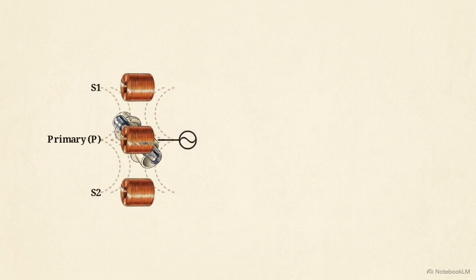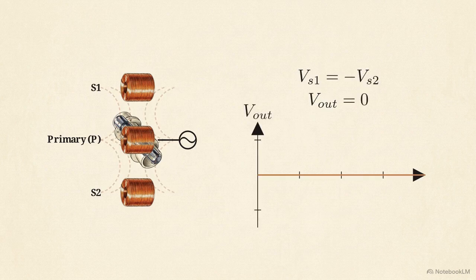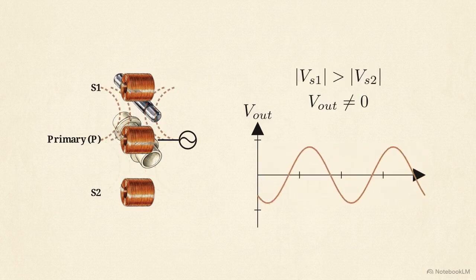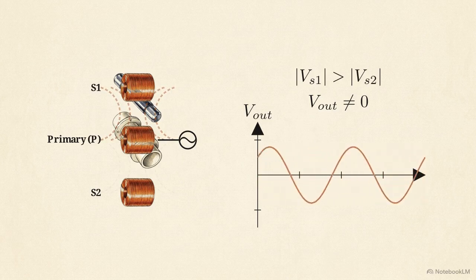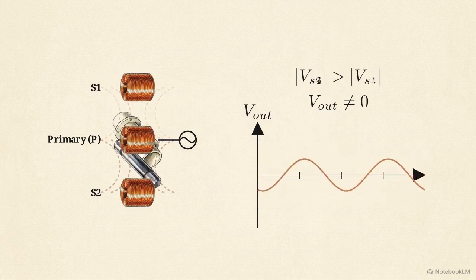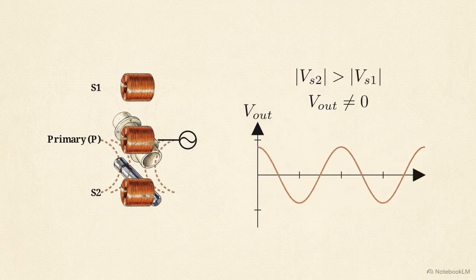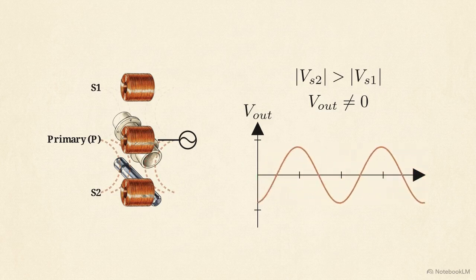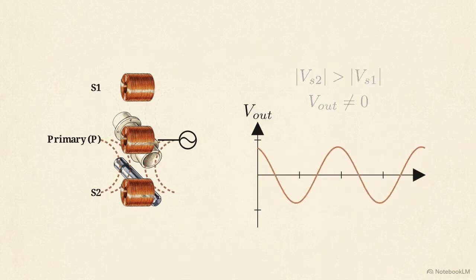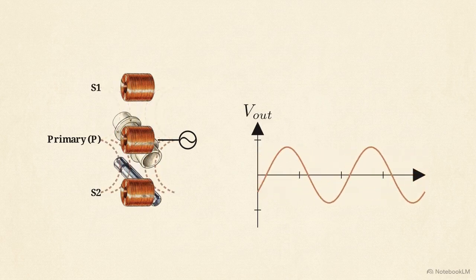In the baseline state, an alternating current drives the primary coil. When perfectly centered, it provides equal magnetic coupling to both secondaries. Wired in series opposition, voltage S1 equals negative S2, canceling out for an output of 0. If the core slides upward, the magnetic coupling shifts. Flux lines concentrate toward the top coil, making S1 greater than S2, generating a non-zero output voltage. Conversely, as the core slides downward, flux concentrates toward the bottom coil. S2 is now greater than S1, generating a non-zero output voltage exactly 180 degrees out of phase.